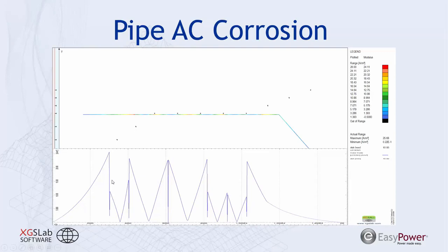Here, we can see the rather dramatic effect that those insulating joints make on that amps per meter squared value, as you can see, these drastic peaks occurring at each one of the insulated joints. Now, one thing to consider again is that each analysis is unique, and there are many options available when trying to mitigate AC interference, but it is very dependent upon the system owners as far as what is actually going to be a practical solution and what may actually cause more harm.